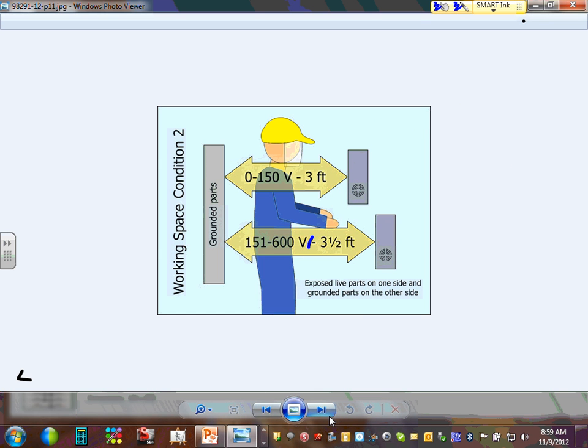When you go to condition 2, now condition 2, grounded parts. Here's a grounded part. This block wall is a grounded part. So if you have a panel and in the front of it is a grounded part. So suppose that this wall is here, grounded, right? So can you guys see the distance? If it's 208, this is for my 208 system and my 240 system. This one is for the 480 system, right? For the 240, 208 system, I still need 3. For the 480, what do I need? They added how many? Extra what? Half a foot. Can I have a thumbs up, Chad? That's it. That's for the grounded.